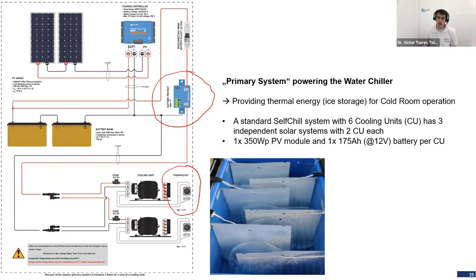So you see here the water chiller from the top, the thermal storage, and this is the ice. I hope you can recognize it. These ice blocks are around the evaporator plates. This is all ice, and the rest is cold water. So for example, here I see water. So we always have a mixture of water and ice, and the primary system is providing energy to the cooling units, and the cooling units are running until the temperature goes to -5 degrees.